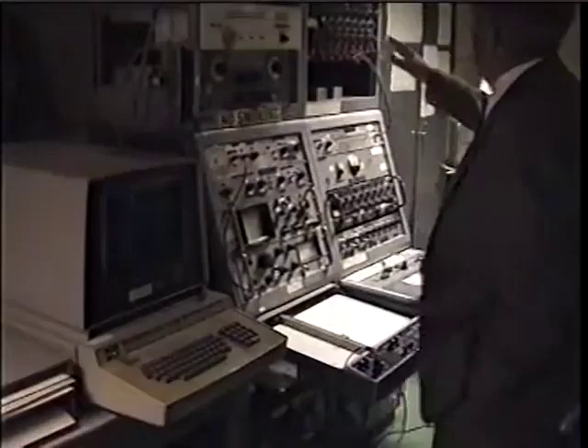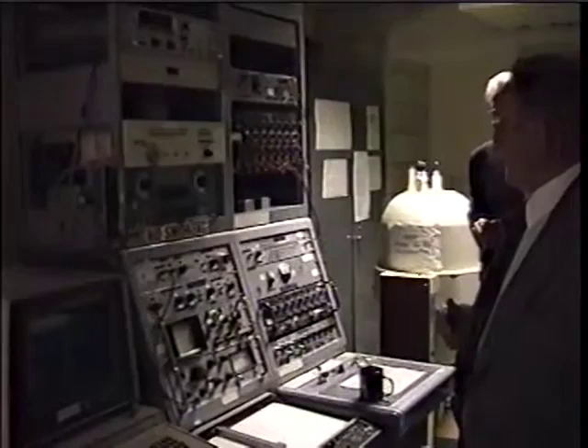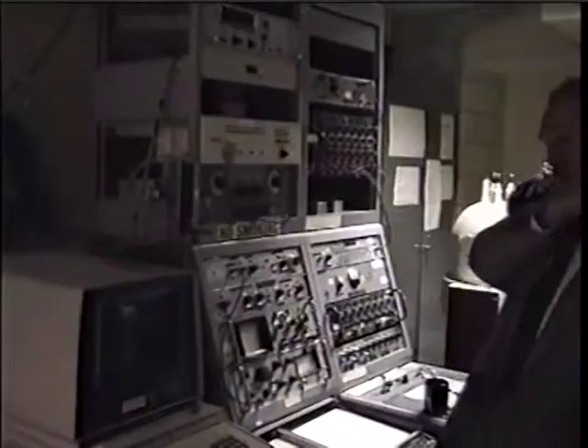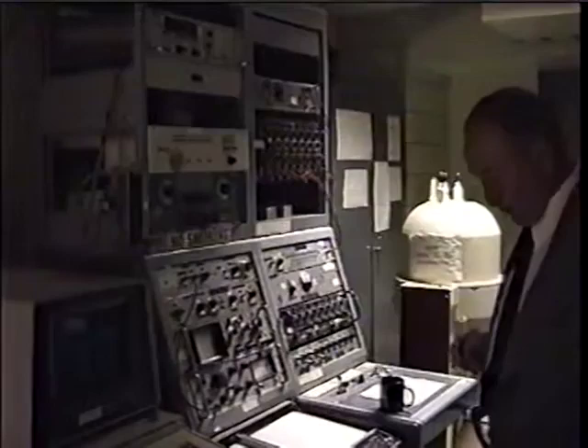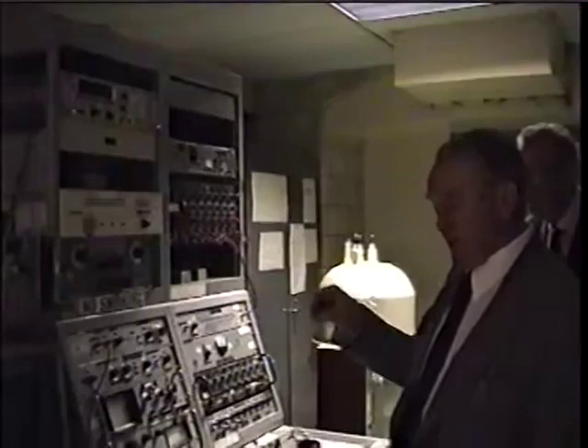So the experiment would run like this. You just type the number of scans, the sweep width, from where to scan, and then the computer would do the job by sending the frequency information into the Tektronix. It was led by cables into this synthesizer here, and at the end to the magnet we would get the appropriate frequency, which was in the latest time 620 megahertz for protons, okay? And it would make eventually 2,000 pulses per second. At the same time, the frequency would move, and after each pulse, the data would be accumulated, and we would get what we call raw data.